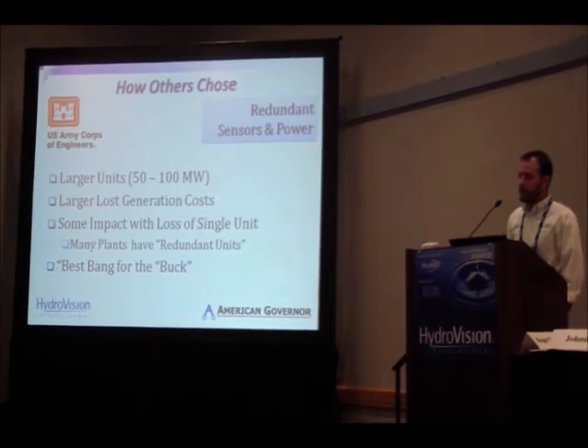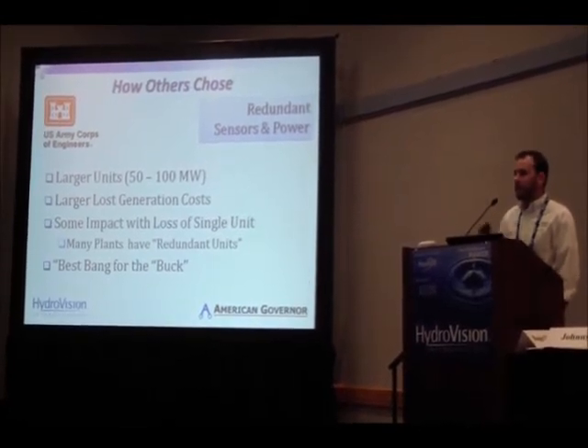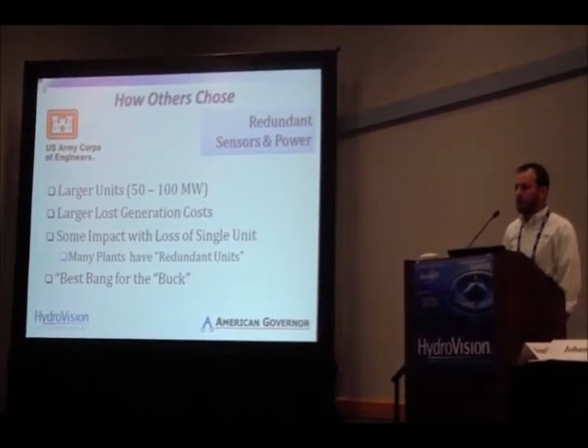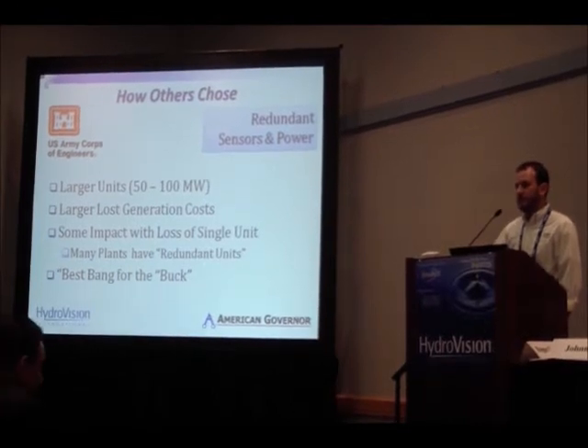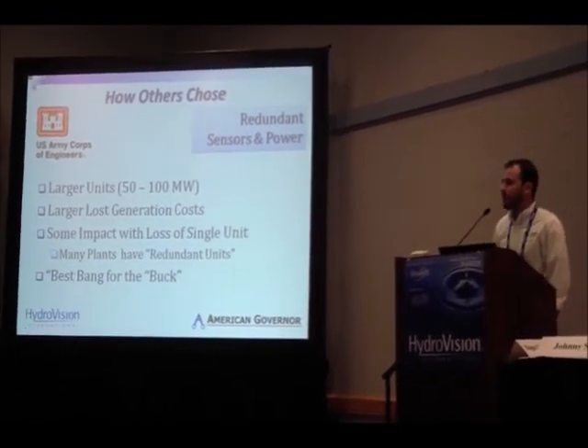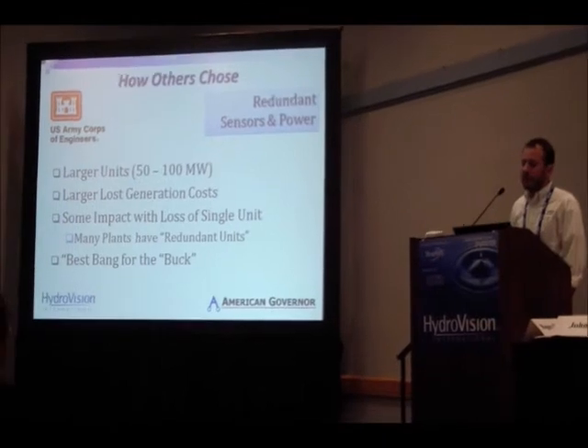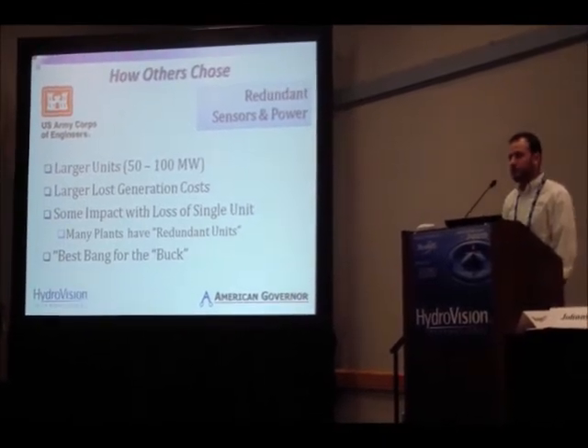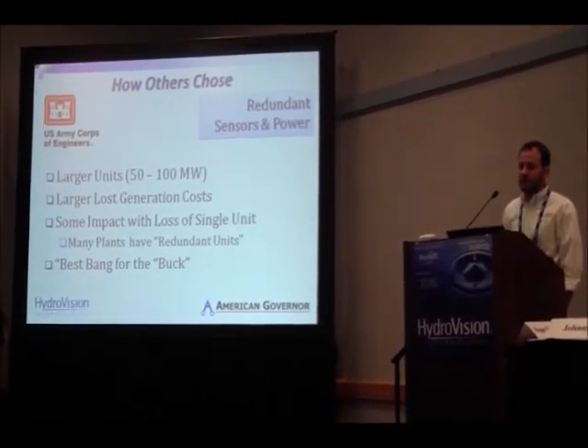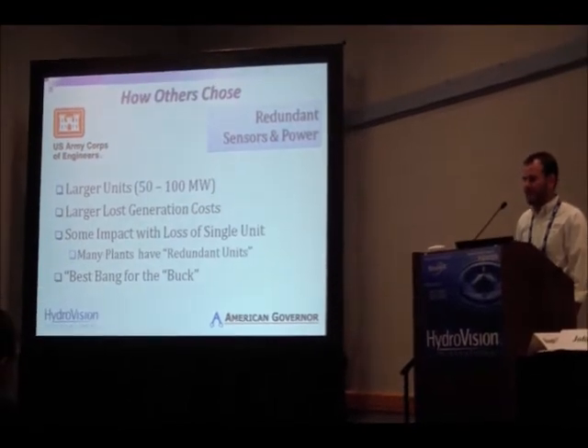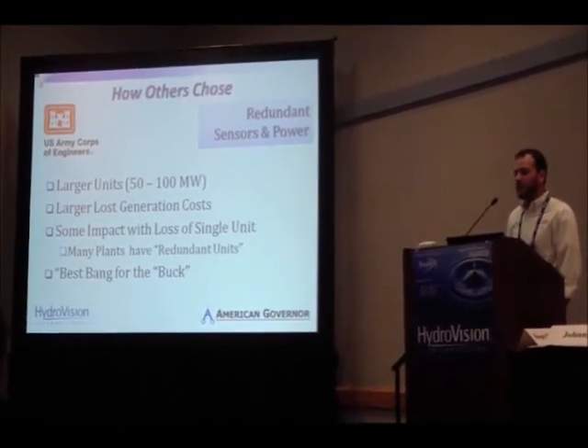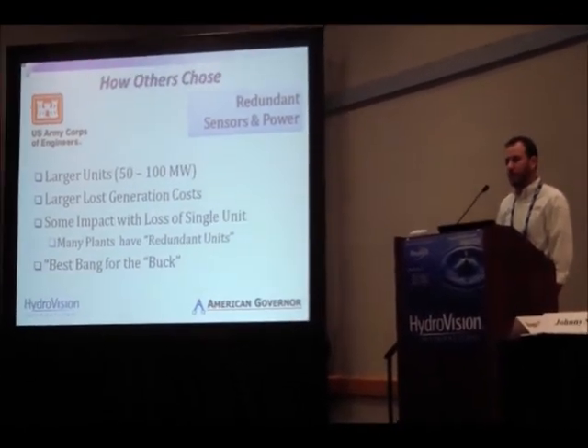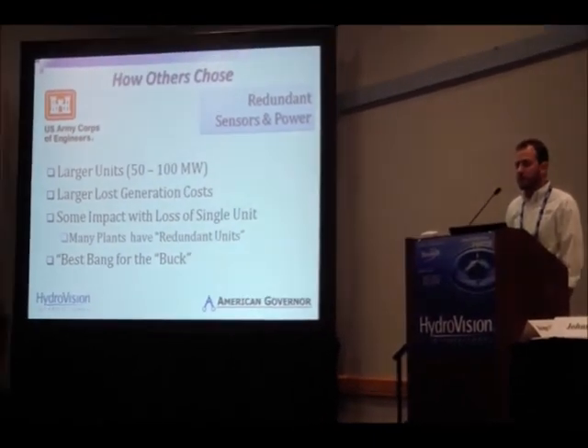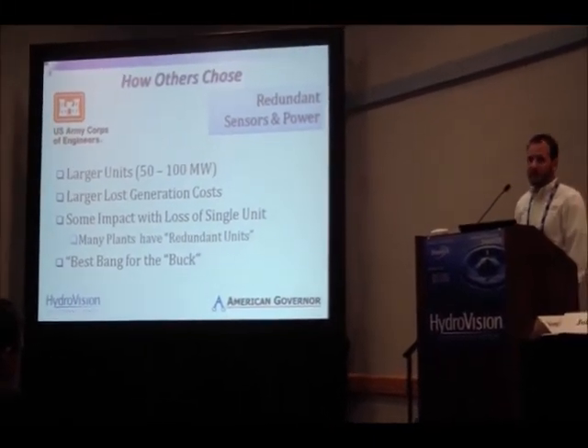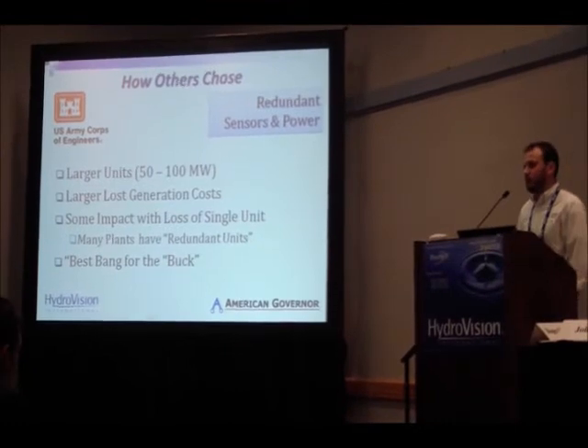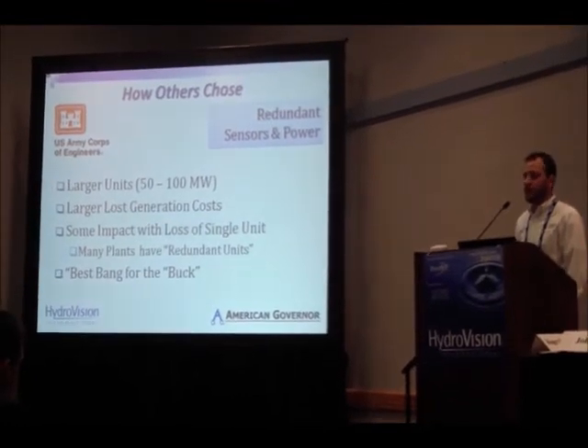But in their favor, these plants have redundant units. So maybe unit 7 goes down, unit 8 wasn't running at the time, they can bring that up. So there's a level of backup there. So these aren't critical failures, they're costly failures, but they will not result in any significant fines, and there are backup options. That's why they choose redundant sensors and power supplies. And it's also the best bang for your buck. It's the easiest to implement, and it gives you the biggest boost in availability for the least cost.